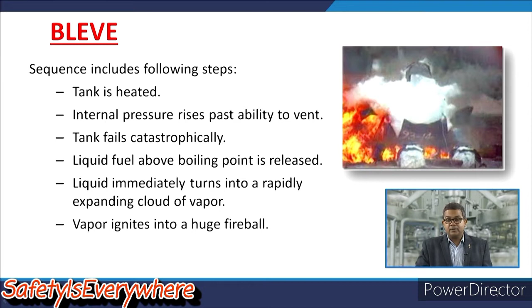So, let us summarize the sequence of a BLEVE. There are different sequences in the BLEVE. Once the tank is heated, the internal pressure rises past the ability to vent. The tank fails catastrophically, the safety devices fail or it ruptures in some way, and liquid fuel above its boiling point is released to the atmosphere. The liquid immediately turns into a rapidly expanding cloud of vapors, and the vapor ignites into a huge fireball. So, you can imagine how destructive it is.